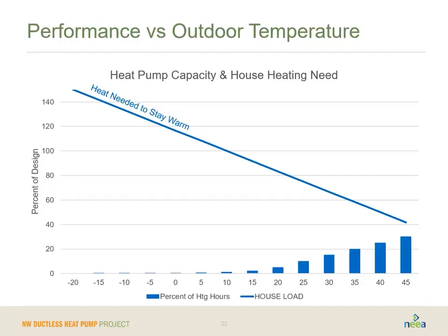So now let's talk a little bit, really going to nerd out here, but I'm going to try and keep it pretty high level. I talked earlier about heat pump capacity versus design load. So the load is how much heat the house needs to stay warm. You can see this blue line that starts at the upper left and goes to the lower right. That is the heat that's needed at different outdoor temperatures to keep the house at a constant temperature.